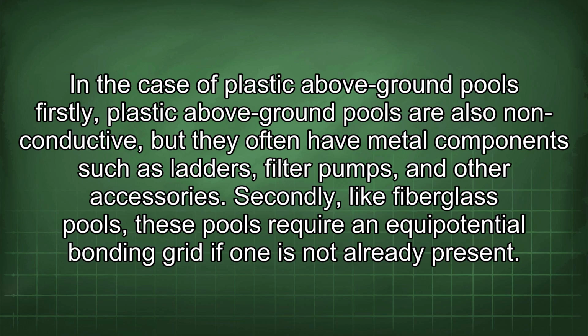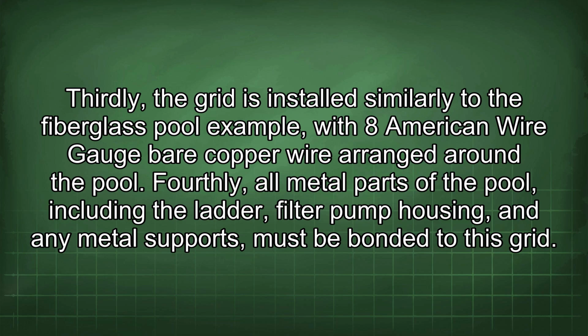Secondly, like fiberglass pools, these pools require an equipotential bonding grid if one is not already present. Thirdly, the grid is installed similarly to the fiberglass pool example, with 8 American wire gauge bare copper wire arranged around the pool. Fourthly, all metal parts of the pool, including the ladder, filter pump housing, and any metal supports, must be bonded to this grid.